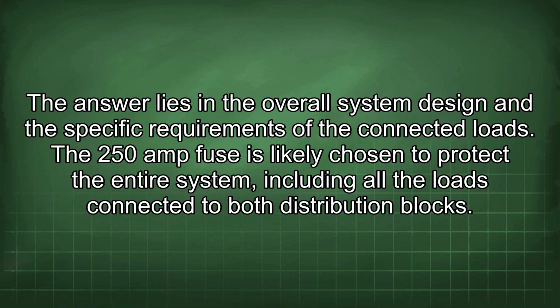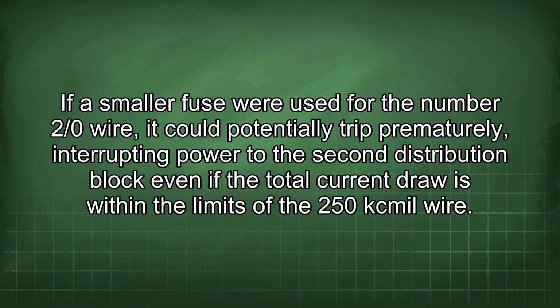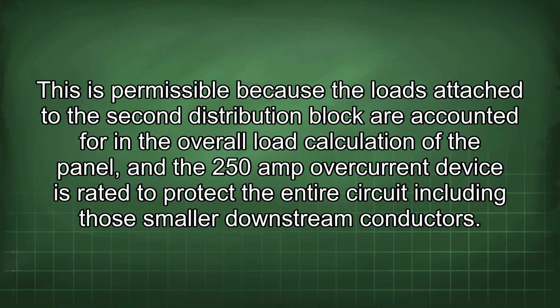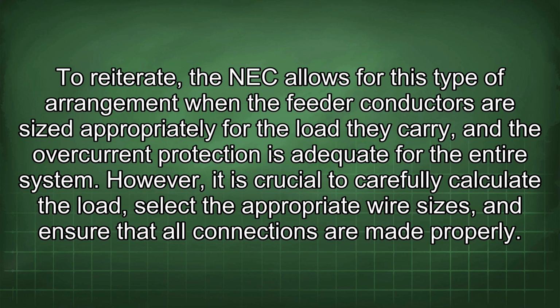The 250 amp fuse is likely chosen to protect the entire system, including all the loads connected to both distribution blocks. If a smaller fuse were used for the number 2/0 wire, it could potentially trip prematurely, interrupting power to the second distribution block even if the total current draw is within the limits of the 250 kcmil wire. This is permissible because the loads attached to the second distribution block are accounted for in the overall load calculation of the panel, and the 250 amp overcurrent device is rated to protect the entire circuit including the smaller downstream conductors. To reiterate, the NEC allows for this type of arrangement when the feeder conductors are sized appropriately for the load they carry, and the overcurrent protection is adequate for the entire system.